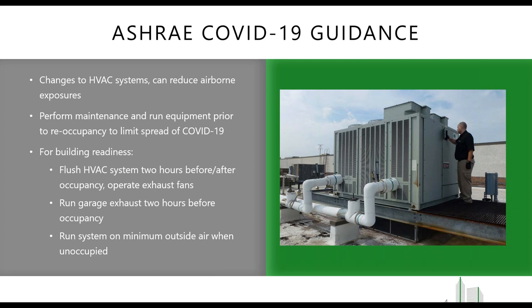And then even when the building is unoccupied, they want you to keep those outside air dampers open and run the systems on minimum outside air. So I know what you guys are thinking. That all sounds great in theory, but that's basically the opposite of what all these energy programs that we've been working on for years have been doing, right? We're trying to keep buildings as energy efficient as we can when they're unoccupied, but ASHRAE is saying we need to keep that ventilation going in the building even when occupants aren't there.